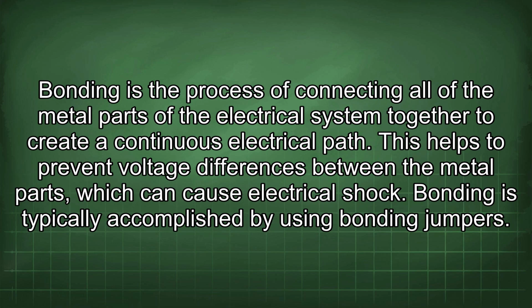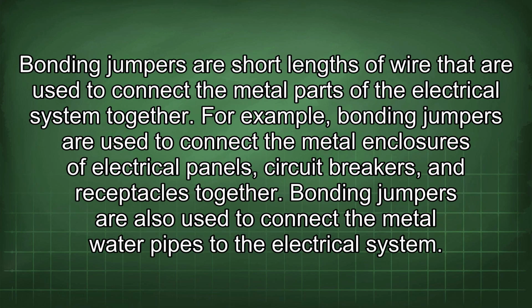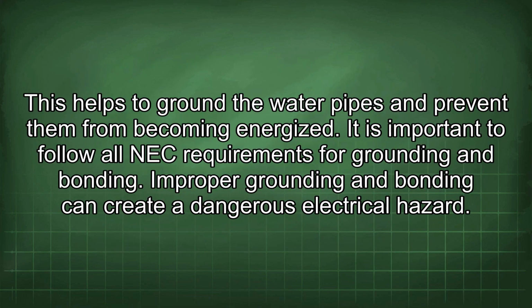Bonding is typically accomplished by using bonding jumpers. Bonding jumpers are short lengths of wire that are used to connect the metal parts of the electrical system together. For example, bonding jumpers are used to connect the metal enclosures of electrical panels, circuit breakers, and receptacles together. Bonding jumpers are also used to connect the metal water pipes to the electrical system. This helps to ground the water pipes and prevent them from becoming energized. It is important to follow all NEC requirements for grounding and bonding. Improper grounding and bonding can create a dangerous electrical hazard.